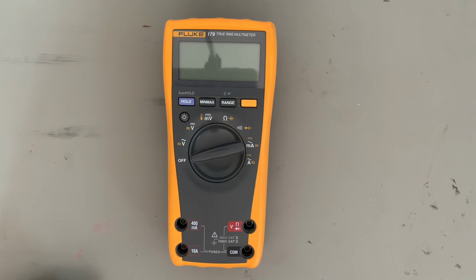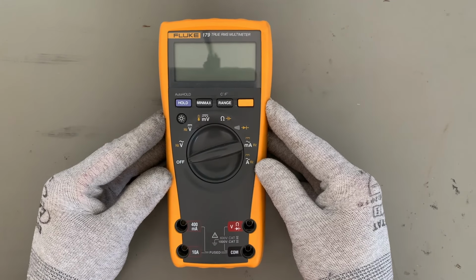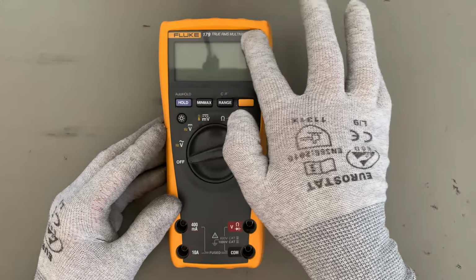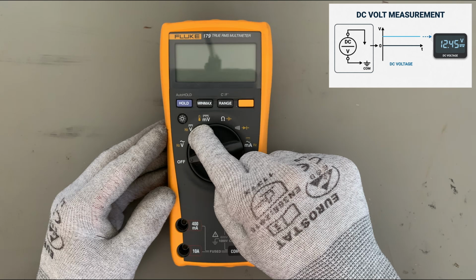Now the dial. Every position has a primary function, and most have a second function hidden behind the yellow button. AC volts measures the effective value of alternating voltage. Press yellow and you get frequency in Hertz instead. Use it for mains voltage, transformer outputs, and hunting down noise. DC volts, batteries, power supply rails, anything steady. This is where you will spend most of your time.